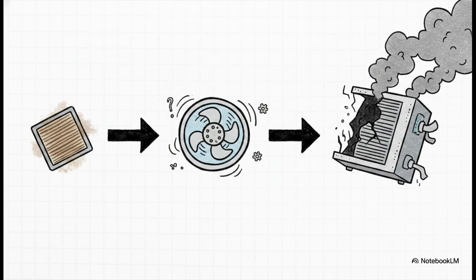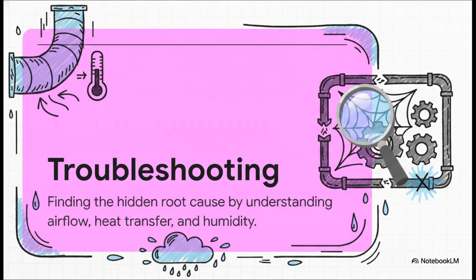As we've seen throughout this explainer, most summer HVAC failures do not start as massive breakdowns. They begin as tiny, misdiagnosed symptoms: a dirty filter, a slightly closed damper, maybe a failed sensor that no one noticed. It really comes down to troubleshooting over guessing. Because proper troubleshooting means stepping back. It's about understanding the complex but completely logical relationships between airflow, thermodynamics, and humidity control, so you can track down the actual, hidden root cause. It's about diagnosing the system as a whole, rather than just blindly throwing expensive new parts at a sweaty problem.